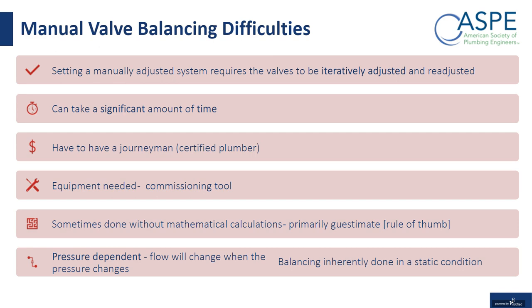So the problems with manual balancing valves, which I'm sure a lot of you have experienced, is that number one, to balance the system, it takes labor and it's an iterative process. So let's say, for instance, you have 10 risers or branches in a domestic hot water system. As you go through balancing each one, setting the balancing valve to get the right temperature, and you go through all 10 of those, now you have to go back again because every time you adjust the flow in one valve, you're impacting the flow in all the other branches or risers. So basically what you do is just keep on going through this iteratively until you get them all at the right temperature. And this can take a significant amount of time, especially the more branches or risers you have, the more complex the system, the more difficult it is to get them manually adjusted.